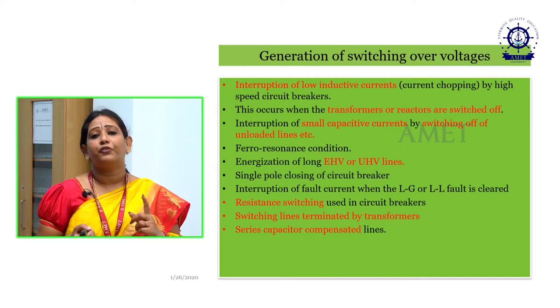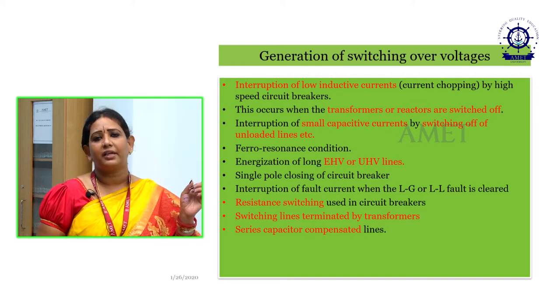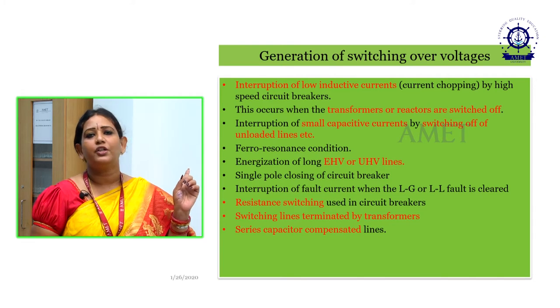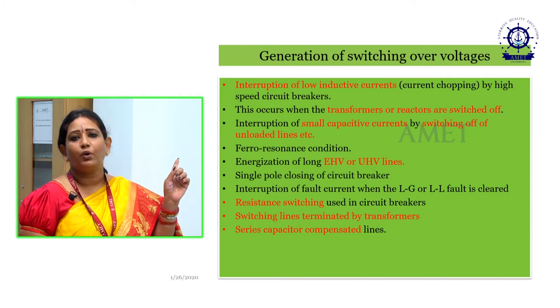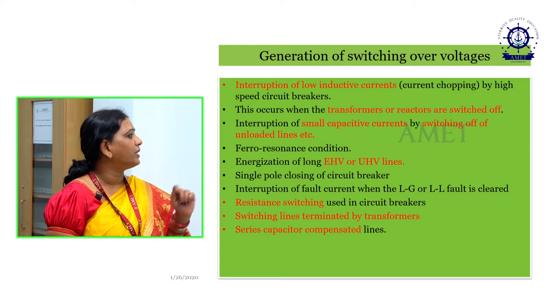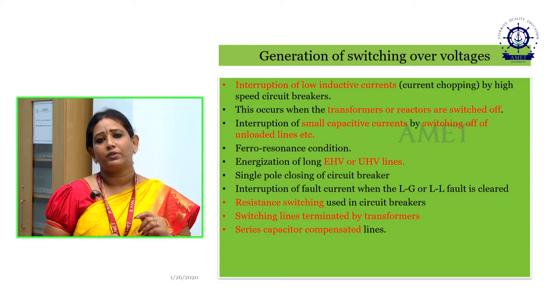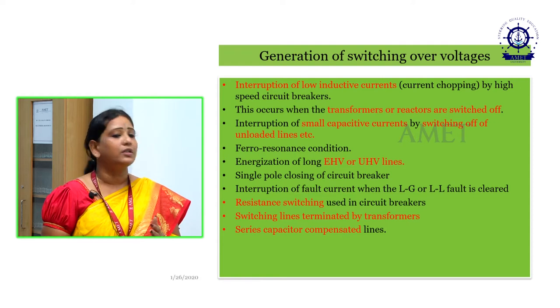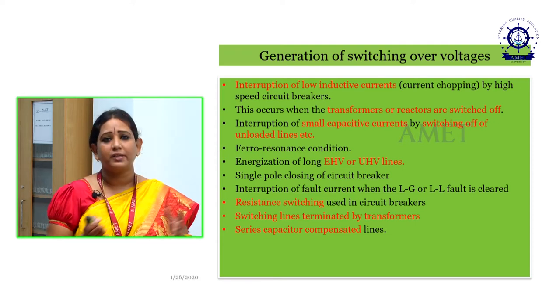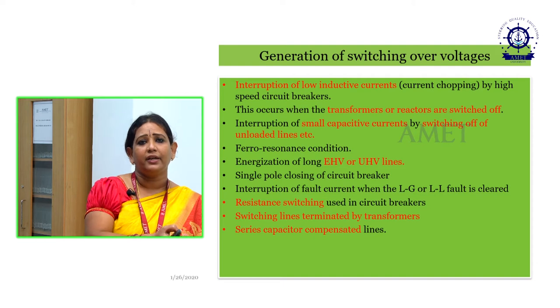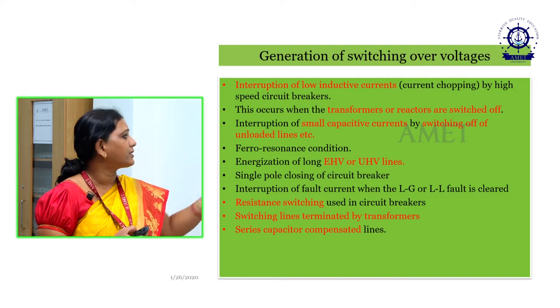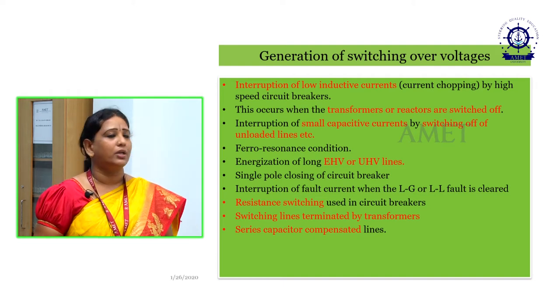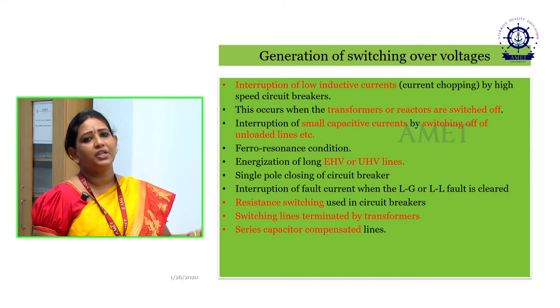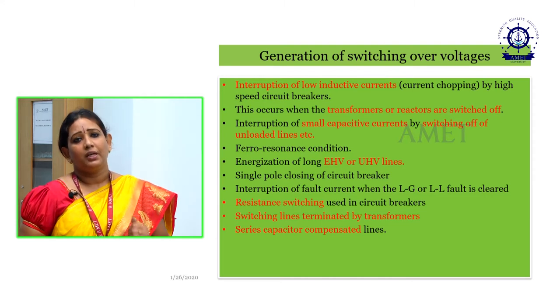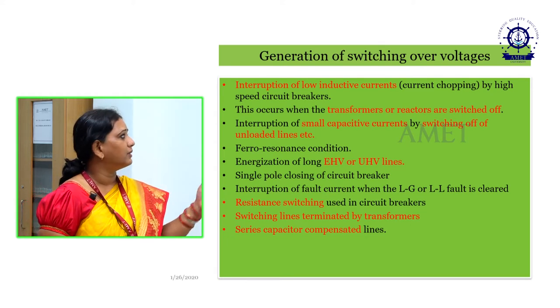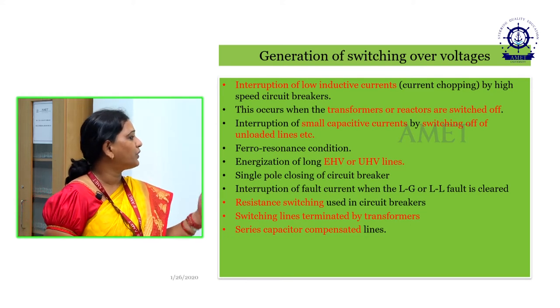And then next is ferroresonance, which is really a challenging condition that should be taken care of and has to be avoided. The next is the energization of long extra high voltage lines. When we connect the EHV lines, extra high voltage or ultra high voltage lines, to the source, say the generator, it is also a sudden action. That creates an over voltage, which we call a switching over voltage, because we are switching into the system and connecting to the supply. Then next comes resistance switching.